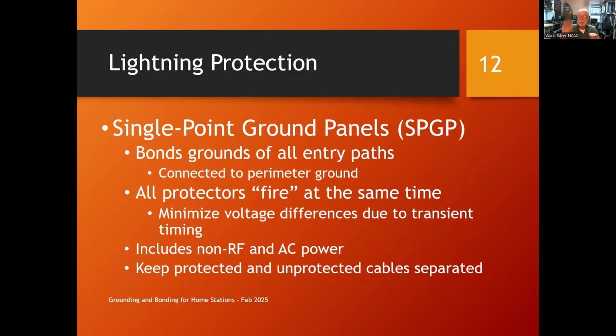Remember, we talked about the destructive voltage differences where suddenly this part of the station is at this voltage and later it's like this. That's a destructive voltage difference. If you can put all your protectors in the same place, grounded to the same panel, they will fire at the same time and everything goes up and down together, not up over here and then 10 microseconds later up over here. That's plenty of time for a destructive voltage difference to cause a problem. So all of your protectors fire at the same time. That's why they're all mounted on this panel.